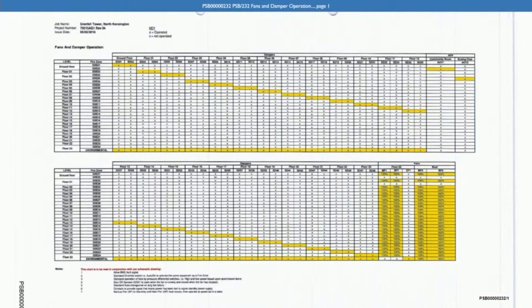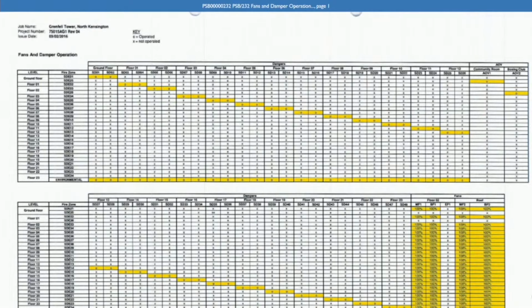You make it a little bit bigger. That shows, for example, if you just look at the first column, which says ground floor, it says it's fire zone 1, and if fire zone 1 activates, damper 1 and damper 2 will open. So that's telling me if you activate fire zone 1, that's the dampers that will open. And if you carry across on that top line, everything else is shown as closed. When you get to where the fans are, it tells you what speed the fans should be running at.